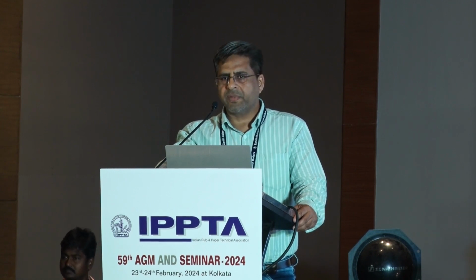Presently, we have 3 turbines synchronized with the grid in a single busbar system. Whenever there is a problem in the grid or something else, the whole system trips, resulting in production loss and thus energy loss also. So we are planning for a double busbar system, where we will run 1 turbine in parallel with the grid and 1 in island mode. In island mode, we will be going for slightly less frequency, so that in case of any loss or tripping, the other system can take care.